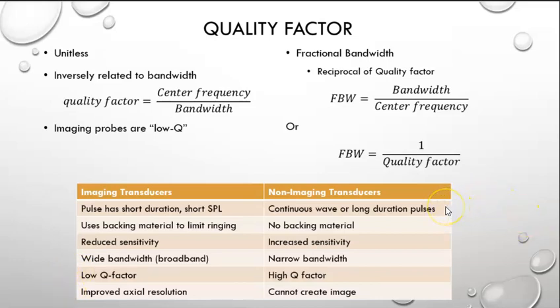Non-imaging transducers have continuous wave or very long duration pulses, and just so you know, non-imaging transducers are used specifically for vascular ultrasound in doing particular types of Doppler measurements of blood flow. So we don't necessarily get an image of the blood flow, but we have very sensitive transducers which can detect the blood flow. So these do not make a picture. They're non-imaging. They are generally continuous wave or long duration pulses.